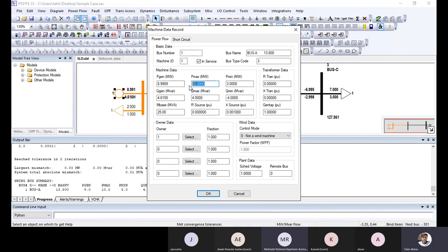Okay. Imagine that this is not a swing generator. So if your Pmax is 10 megawatt, and Pmin is 3 megawatt. Okay, so if you define this parameter Pgen to 5 megawatt, what will happen? Now, because I have added only one generator, that is only the swing, the demand is 7 megawatt. I'm adding a 5 megawatt generator. What do you expect? Because this is a swing, definitely the swing will take care of the demand. Swing will go to 7.